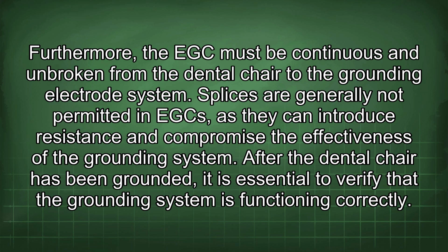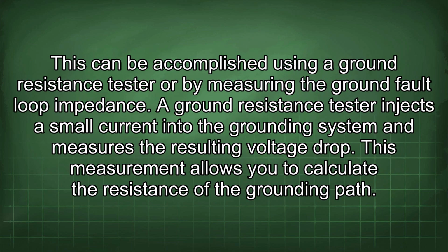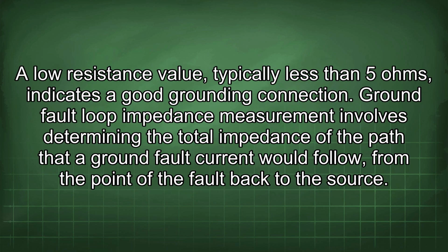After the dental chair has been grounded, it is essential to verify that the grounding system is functioning correctly. This can be accomplished using a ground resistance tester or by measuring the ground fault loop impedance. A ground resistance tester injects a small current into the grounding system and measures the resulting voltage drop. This measurement allows you to calculate the resistance of the grounding path. A low resistance value, typically less than 5 ohms, indicates a good grounding connection. Ground fault loop impedance measurement involves determining the total impedance of the path that a ground fault current would follow from the point of the fault back to the source.